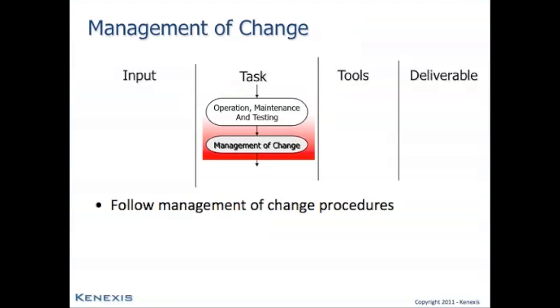Management of change occurs when any modification to the facility occurs. This is more comprehensive than simply looking at changes to the fire and gas system hardware itself. Things as seemingly benign as adding stairs, moving a ladder, adding a piece of process equipment change the effectiveness of the fire and gas detection and suppression system. Adding new equipment may increase the number of leak sources, changing the definition of the zones, possibly changing the categorization of the zones. And at a minimum, these additional pieces of equipment create new obstructions that change the coverage that's achieved by the fire and gas detection arrays.